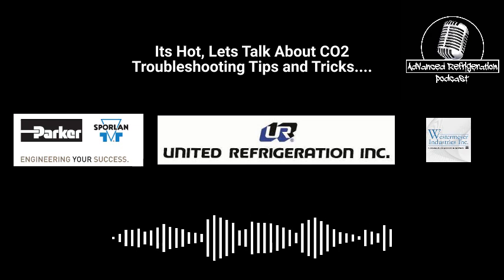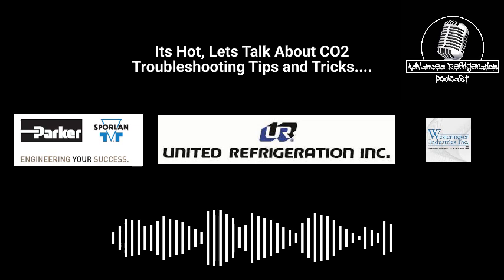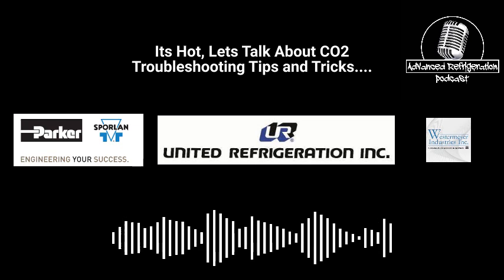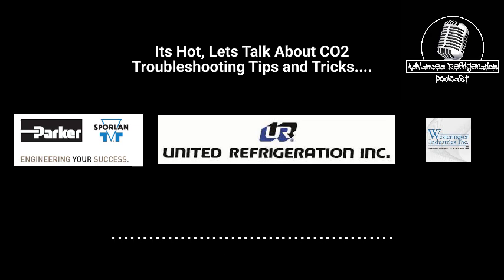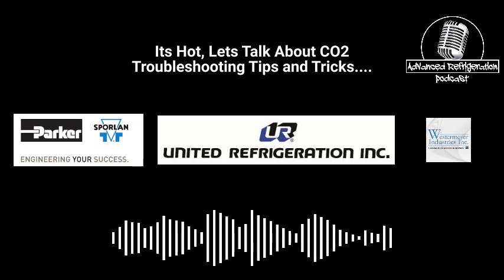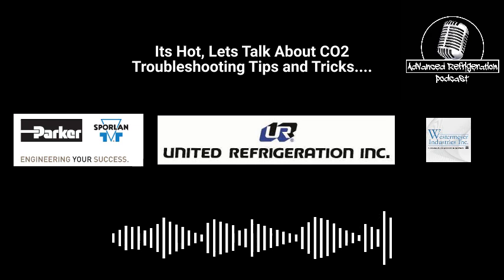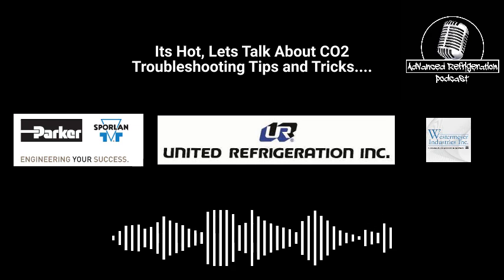But that's another whole issue with not having that sight glass there or being able to see that visibility. And if you have a Danfoss 326 and something's awry with that, you're pretty much screwed because you're not going to be able to see it unless you're on site. You can't see any of those readings without being on site. Unless you're on a Danfoss controller. Correct, which is super not cool that they won't release the Modbus tables. Yeah, that's one benefit you have from that. But everything's supposed to be open protocol now.